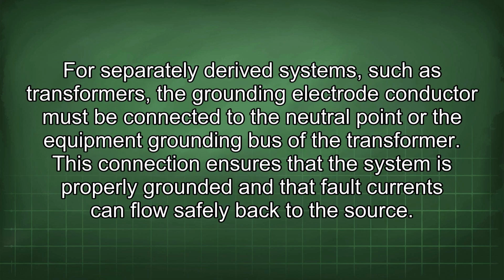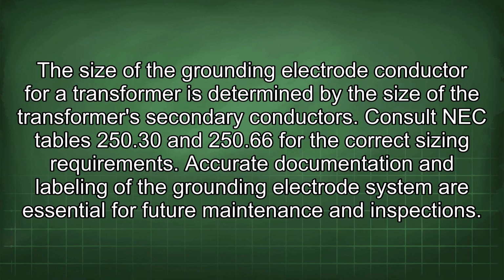For separately derived systems, such as transformers, the grounding electrode conductor must be connected to the neutral point or the equipment grounding bus of the transformer. This connection ensures that the system is properly grounded and that fault currents can flow safely back to the source. The size of the grounding electrode conductor for a transformer is determined by the size of the transformer's secondary conductors. Consult NEC Tables 250.30 and 250.66 for the correct sizing requirements.